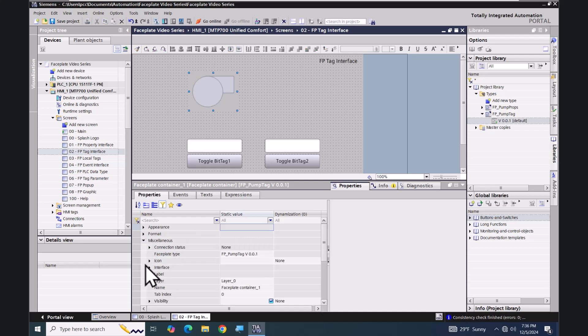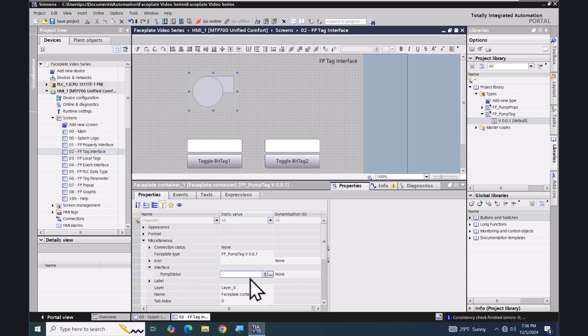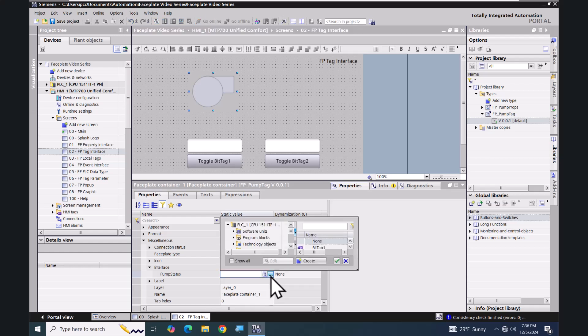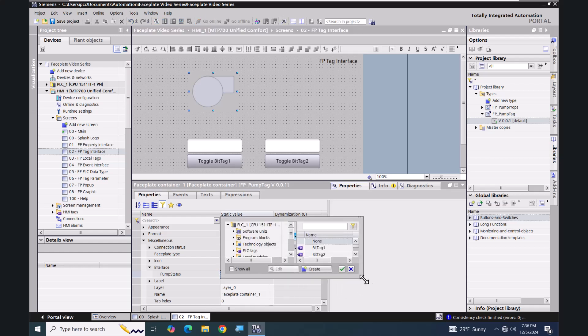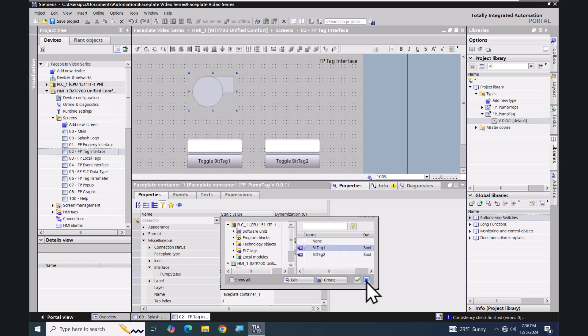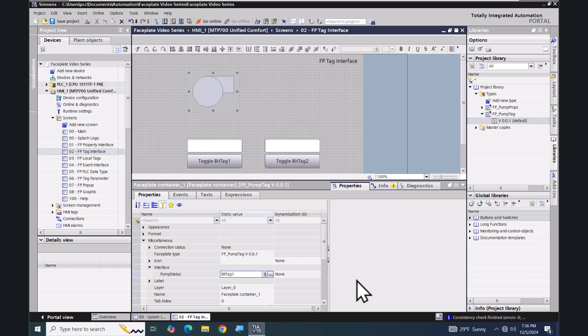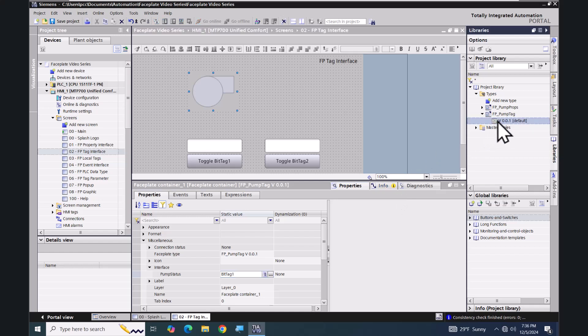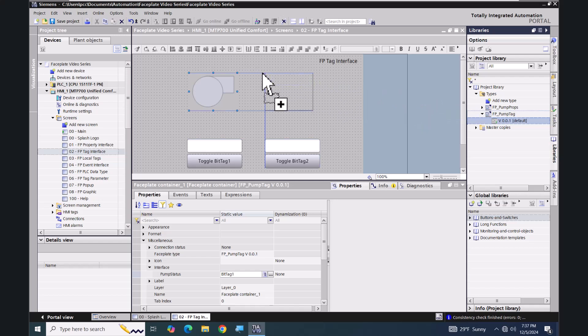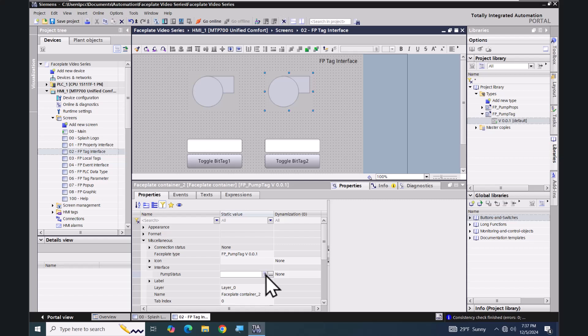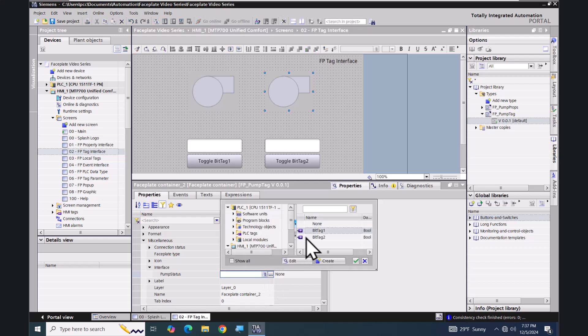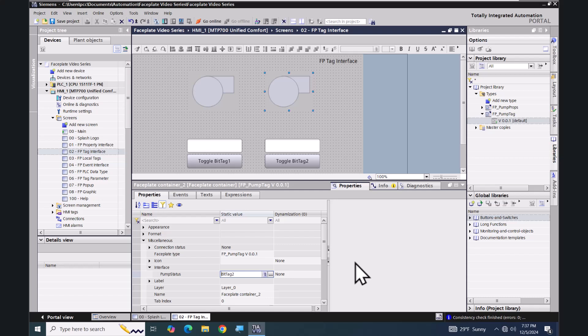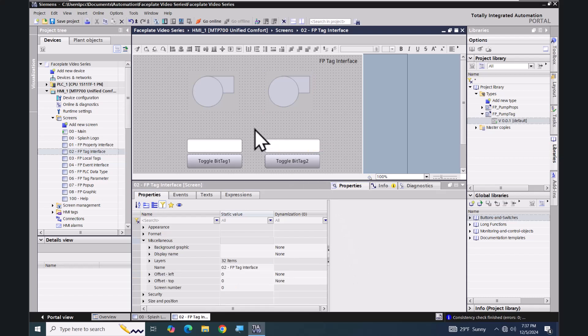I'll go down into the Miscellaneous category and expand the Interface area — this is where you will see the pump status tag entry. I can click in this column and browse for an external tag to link to it. I'll select 'bit_tag_1', which is a Boolean tag. Then I'll drag in another instance of the FP_pump_tag faceplate and for the pump status tag assign 'bit_tag_2'.